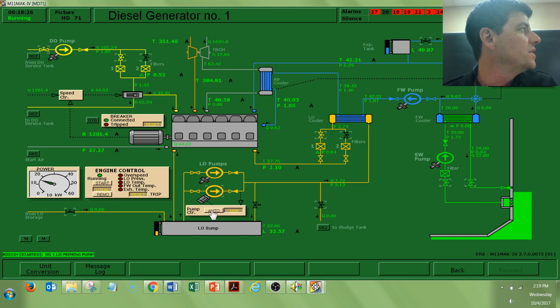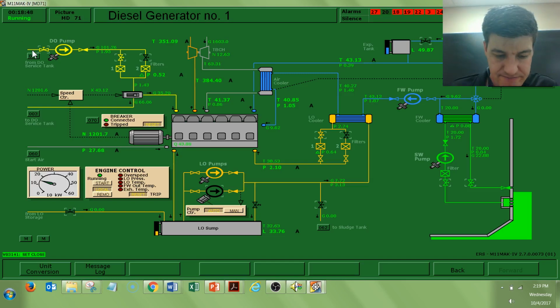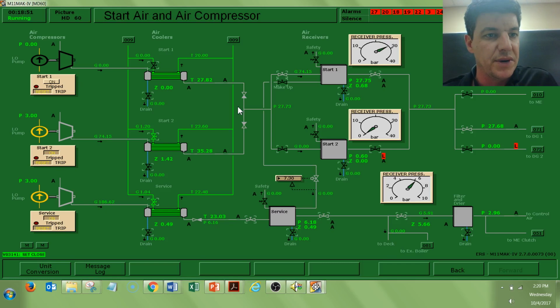This pump, once it's running, we can have it in auto mode and it can turn itself off. I'm not overfilling my sump. I'm not draining it. If I need to up my level, I can do so from storage and then remembering to turn it off once my level is up. On the air compression side, any air compressors that you're operating, I want to have cooling water too. Pathways through. This makeup valve, we can open it up only after we've brought everything up to pressure, so we can keep that guy closed.